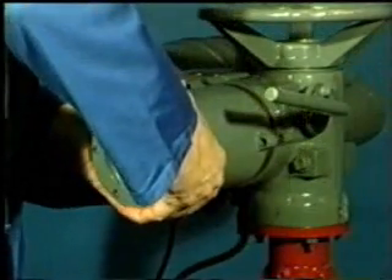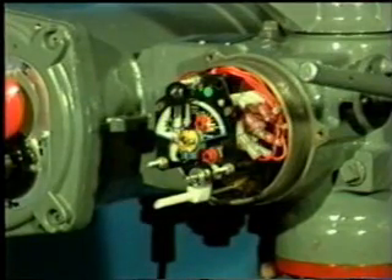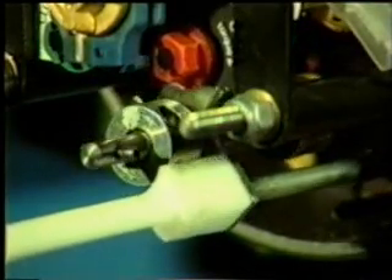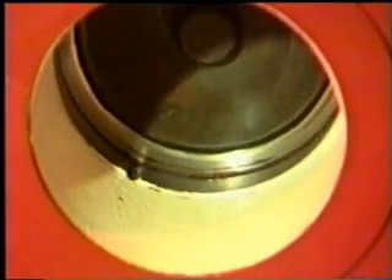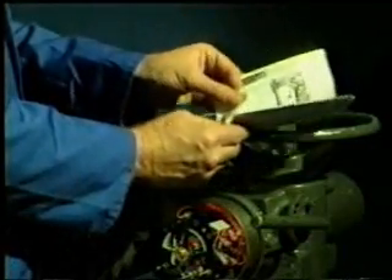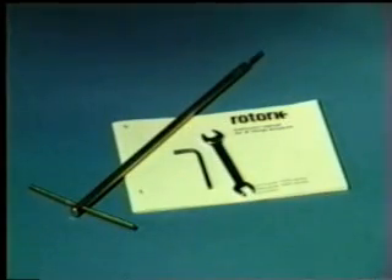It needs a sensitivity almost equal to human hands. The Rotork A-range actuator almost has this by virtue of its unique electromechanical switch. It switches itself off at either end of valve travel, either by sensing it has moved the valve's closing mechanism far enough, or by feeling that the valve is tightly closed. However, careful setting of this switch mechanism is essential to the efficient operation of the valve on which it is mounted. As we shall see, this is not difficult, and these are all the tools you need.